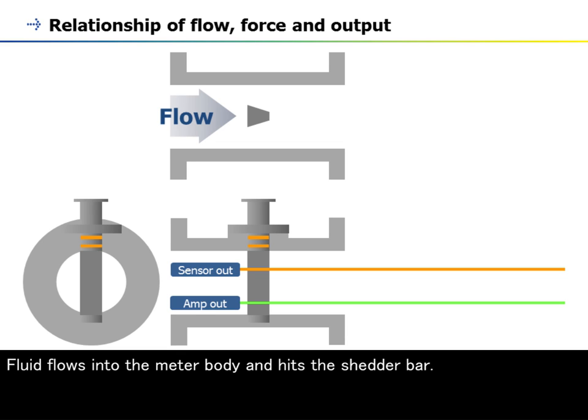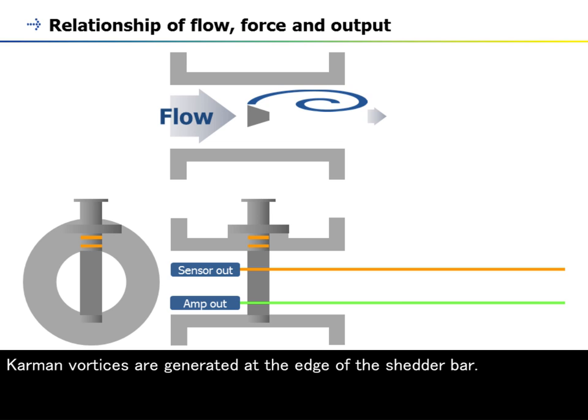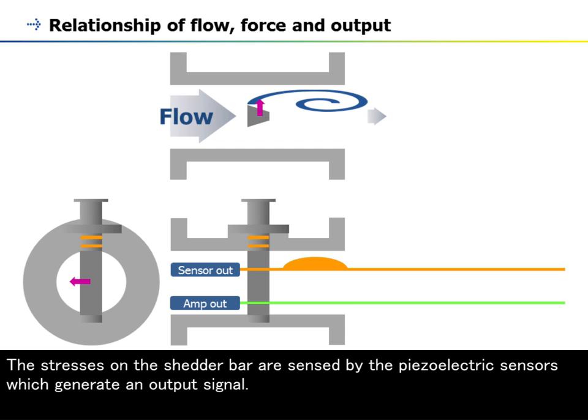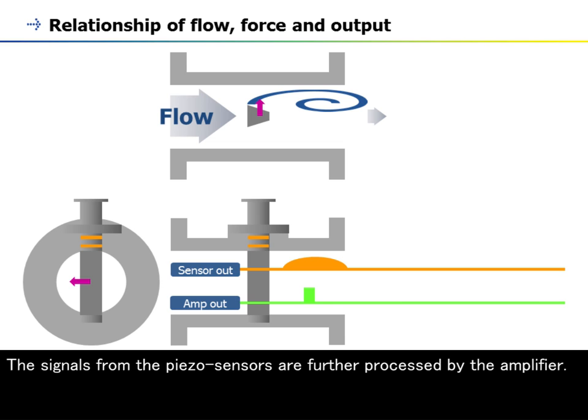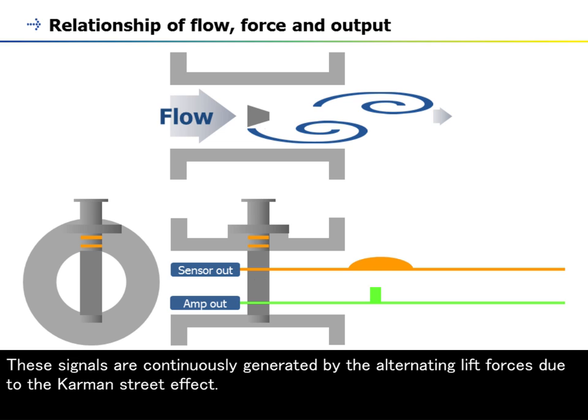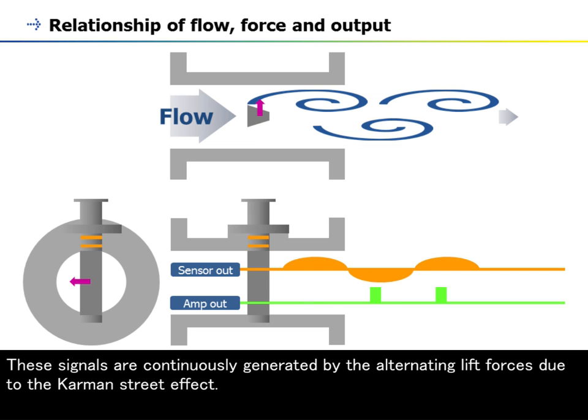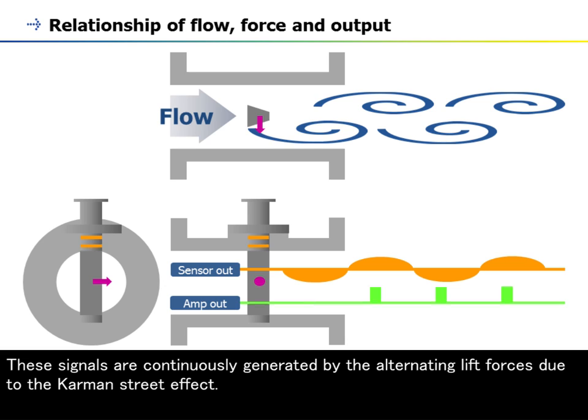Fluid flows into the meter body and hits the shedder bar. Karman vortices are generated at the edge of the shedder bar. Karman vortex generates a lift force in the shedder bar. The stresses on the shedder bar are sensed by the piezoelectric sensors which generate an output signal. The signals from the piezo sensors are further processed by the amplifier. These signals are continuously generated by the alternating lift forces due to the Karman Street effect.